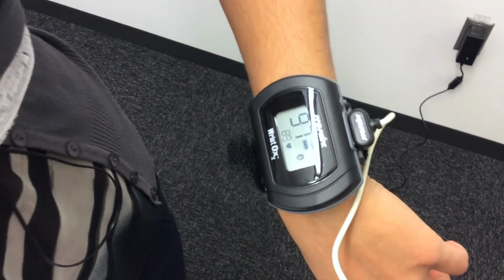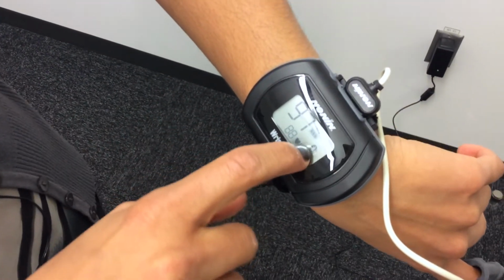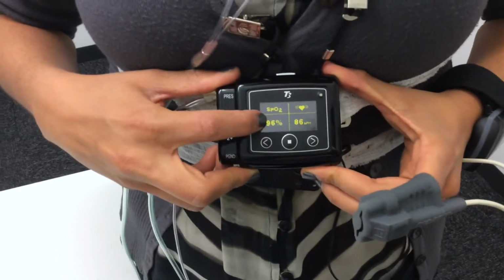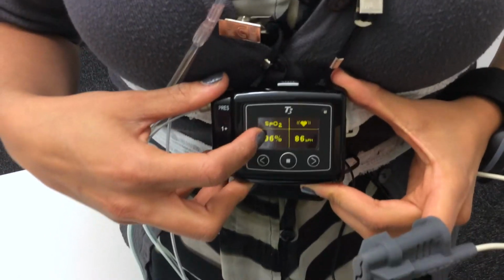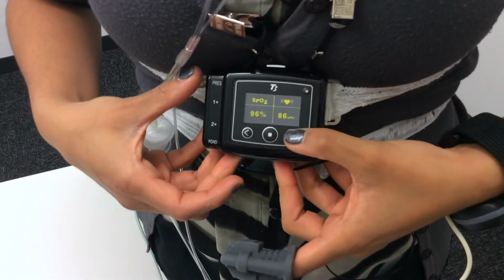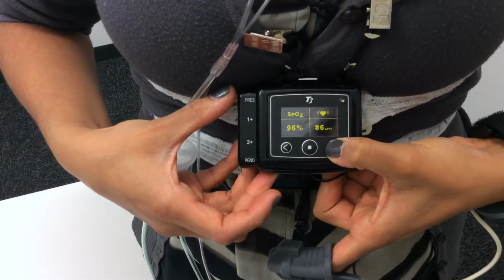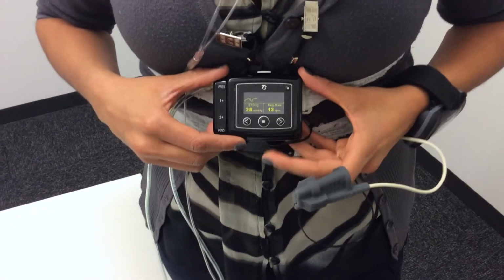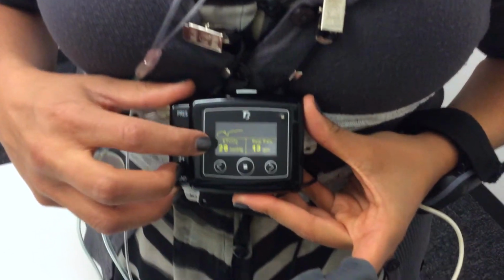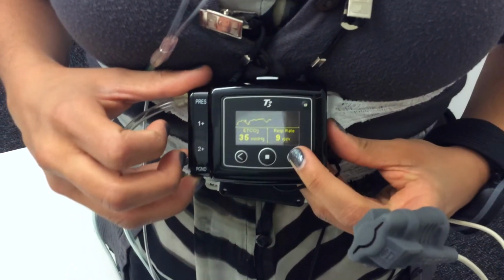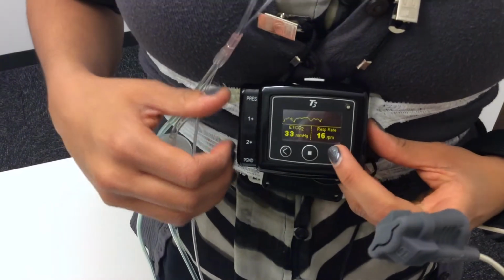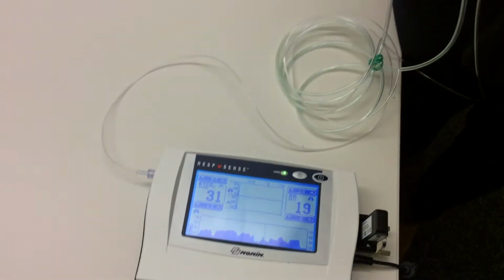And in order to ensure that that connection is taking place, you just have to make sure that you see a Bluetooth symbol right there. Once the connection is established, you will see the numbers on the screen. The next screen, when you press the arrow button, is the connection to the RespSense monitor. So that's between the nasal cannula and the actual monitor. So basically you will find a screen that looks like this, and it will show the EtCO2 number as well as the respiratory rate, and it should match the numbers that are being shown on the RespSense monitor.